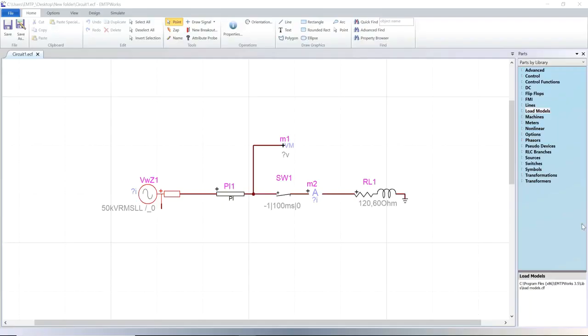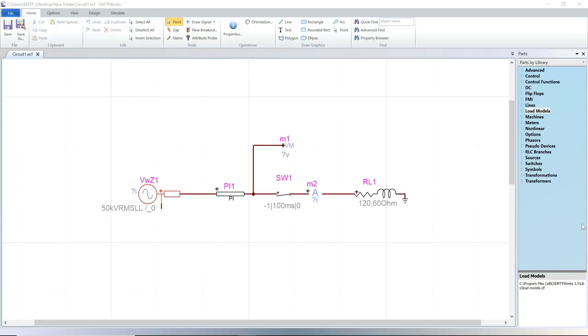In EMTP, the load flow solution is another type of steady state solution. The main difference is that the load flow solution allows entering power constraints without providing lump circuit models for some generation and load devices. The lump circuit models are used in the standard steady state solution option and their parameters are determined by the load flow solution.